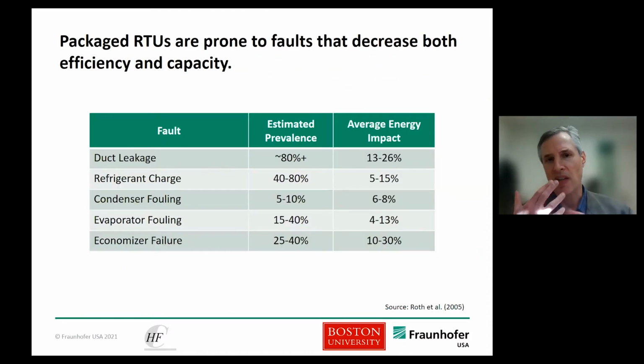So, as I mentioned at the outset, there are a lot of packaged rooftop units. People have done field studies that find that they have faults. Faults such as duct leakage, where the heating or cooling does not go exactly where you want it to go. Refrigerant charge faults, where it's either high or low. If it's low, then the effectiveness in terms of the amount of capacity and the efficiency of the unit drops, in some cases pretty precipitously. And then different kinds of fouling, where essentially your heat exchangers on the evaporator and condenser don't function as effectively as before. And then finally, economizer failure.